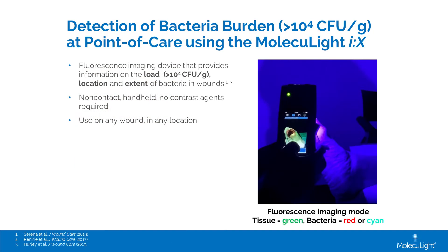So how do we actually use the MolecuLight to detect bacteria? The really cool part about this device is the fluorescent imaging provides information on the load, location, and extent of how much bacteria is in the wound. The device will detect bacteria levels greater than 10 to the 4th logarithmic. Because it's non-contact, it's a handheld product, and you don't need contrast, it makes it very easy for point-of-care bedside testing.